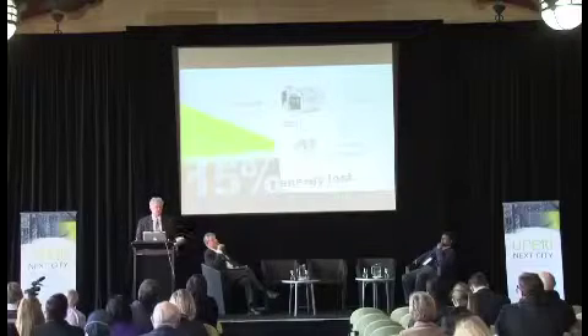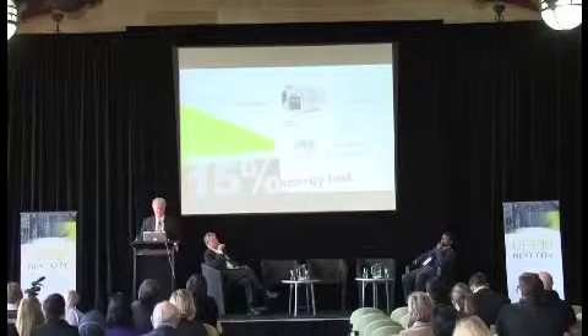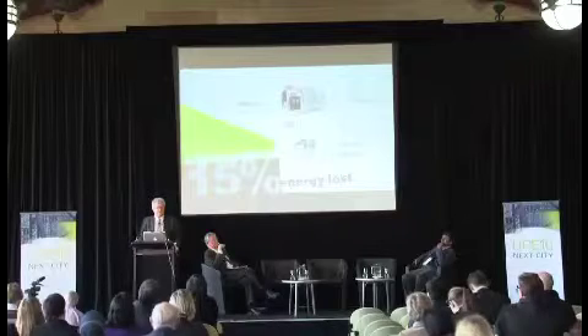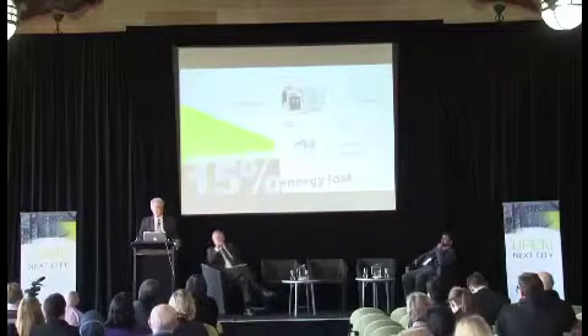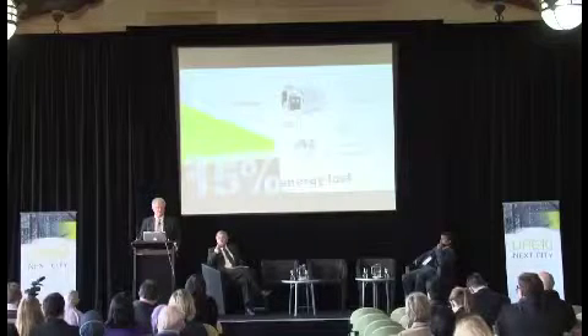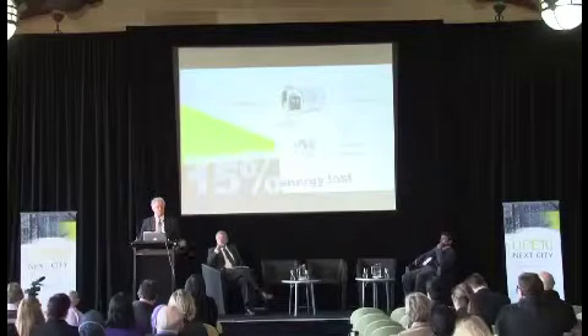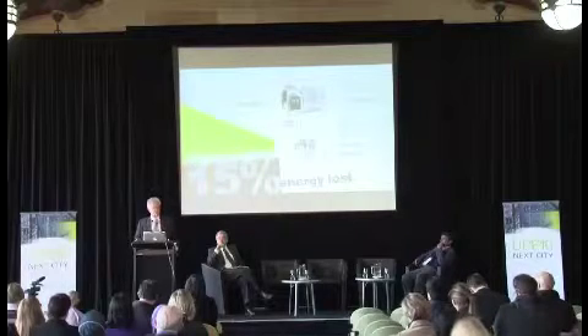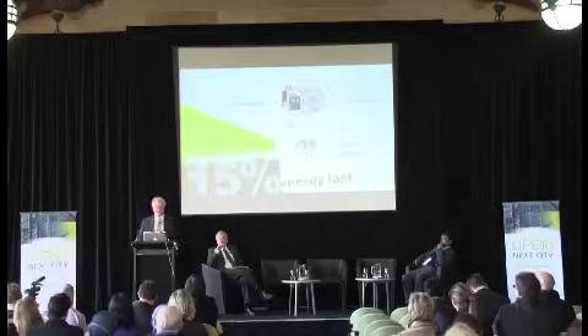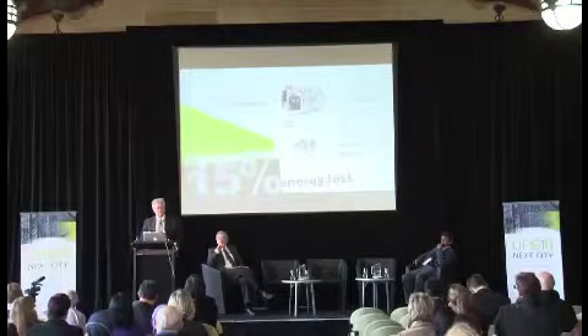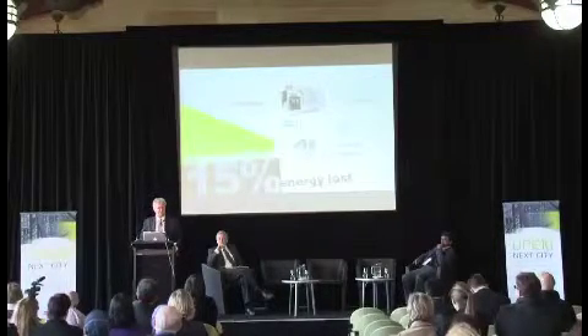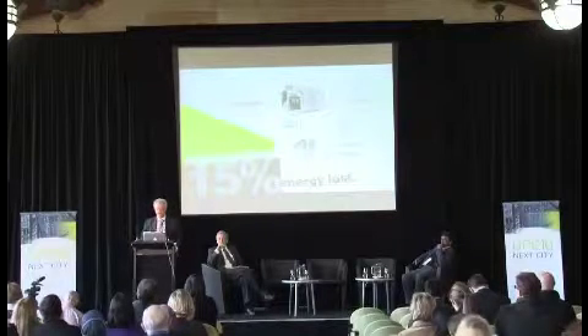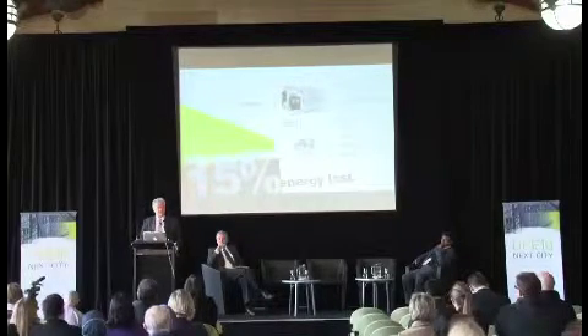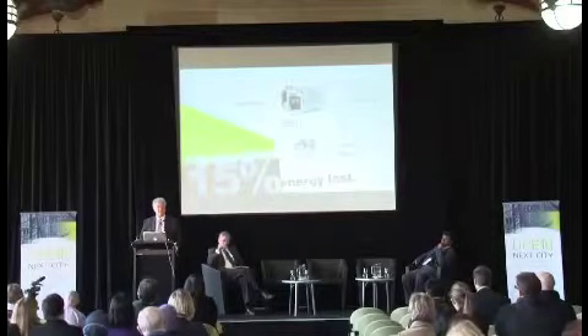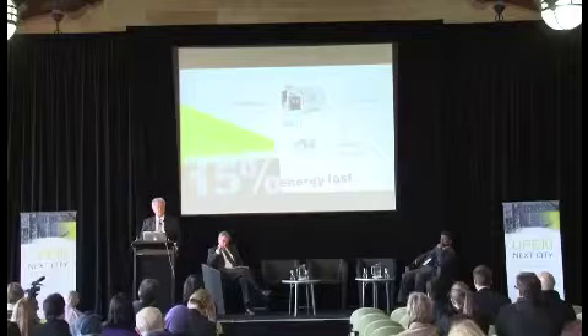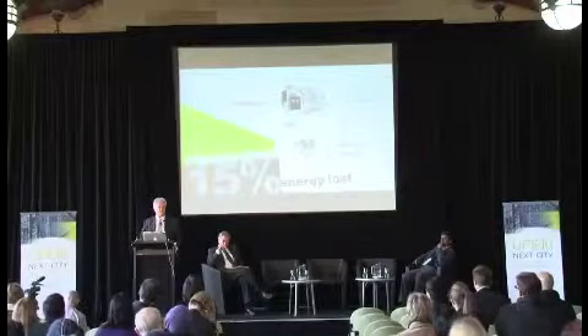Tri-generation is not new in Australia. There are a number of examples, what I call boiler-in-the-basement schemes, where small-scale systems are installed for a NABERS rating or a Green Star rating or whatever. They're all minimised and downsized because of the regulatory barriers to decentralised energy here in Australia, to avoid exporting electricity into the network. So they're not achieving anything like the big greenhouse gas reductions being achieved in Europe, the US and Asia. Typically you'll get an 85% reduction in greenhouse gas emissions by connecting the city together in precincts — that's how it's done elsewhere around the world. We don't have individual systems in individual buildings.